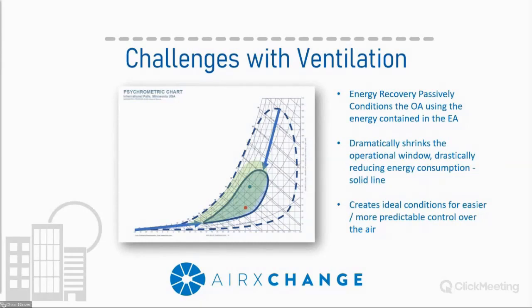Once again, looking at the psych chart at the left, and I'm not trying to make everyone here a psychrometric expert, but I think it does a pretty good job of giving you an image of what the system does. It takes that dotted line, that large operational window, and shrinks it down to that solid line. And really the difference between the two is your energy savings. That reduced operational window provides greater energy savings, and also provides more ideal conditions and more predictable control for maintaining occupant comfort in the space.